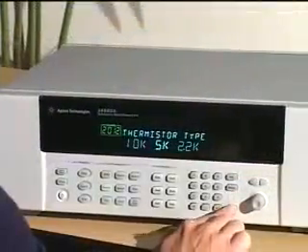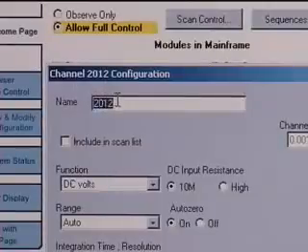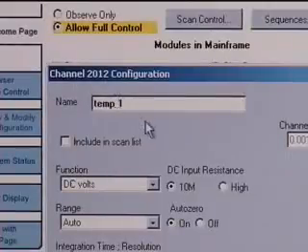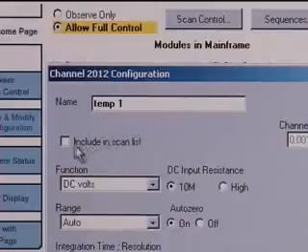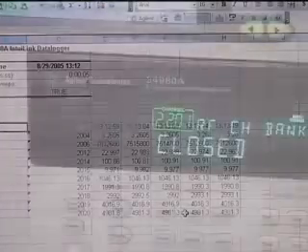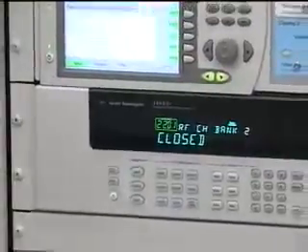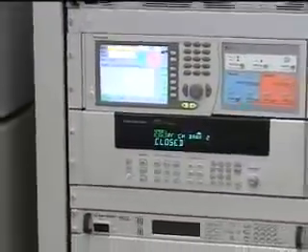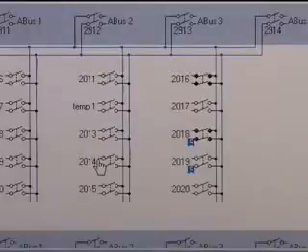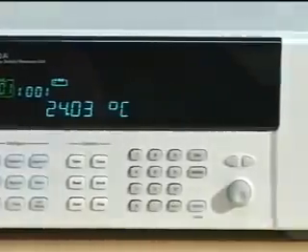For simple tests, the 34980A can be configured from the front panel or via the web interface. Universal channels allow any channel to be configured for a variety of measurements. IntuiLink can log data directly to Microsoft Excel. In test systems which include switching and multimeter measurements, the 34980A provides an economical solution. In addition, it can be used to switch RF signals and provide digital and analog stimulus to a DUT. The 34980A can monitor channels from the bright front panel or remotely via the web interface.